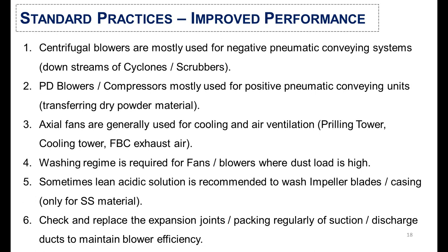We also need to develop a washing regime for fans and blowers where dust load is high. Sometimes it is necessary to wash the impeller blades and casing with a lean acidic solution to maintain the efficiency of blowers — but this is recommended only for compatible blower materials. Additionally, you need to regularly check and replace the expansion joints and packing of the suction and discharge ducts to maintain blower efficiency.